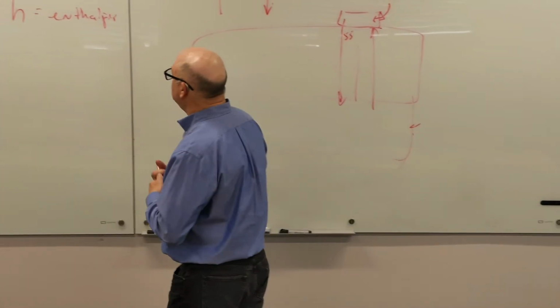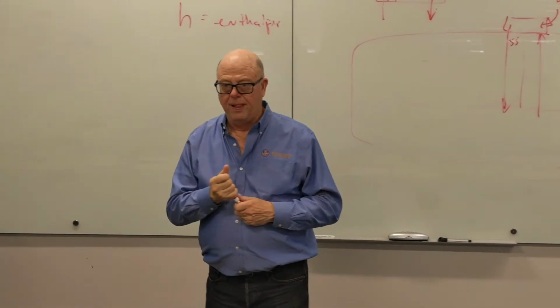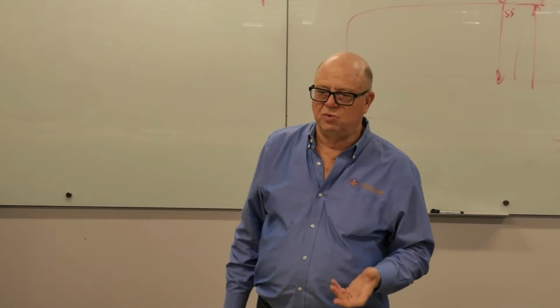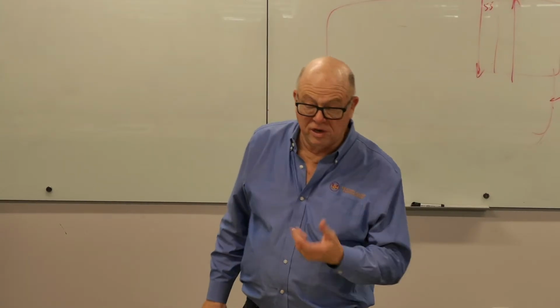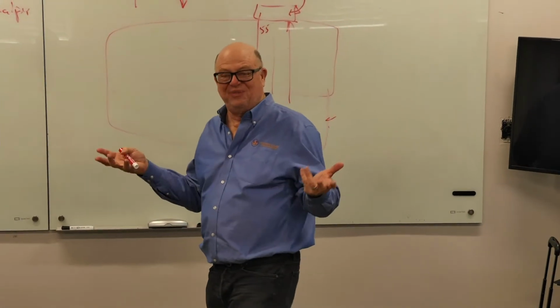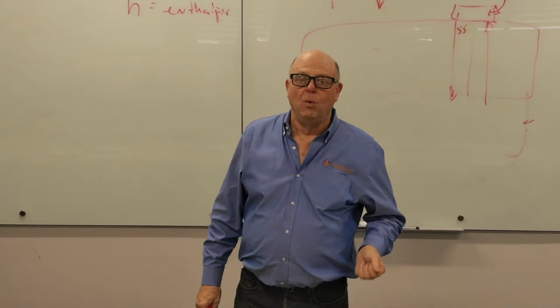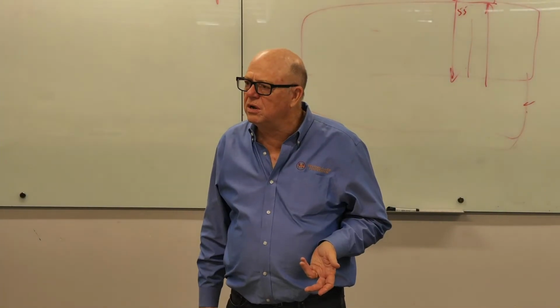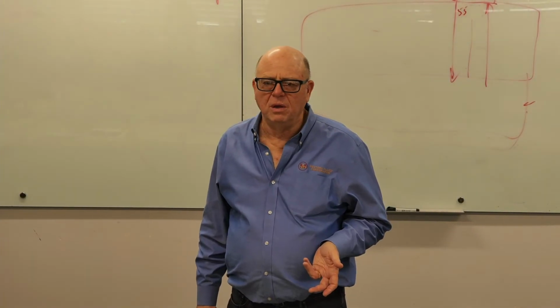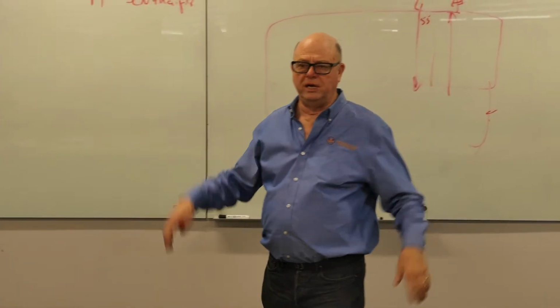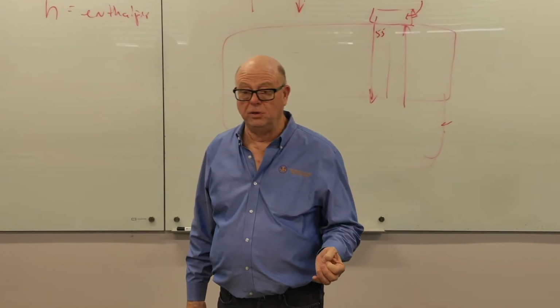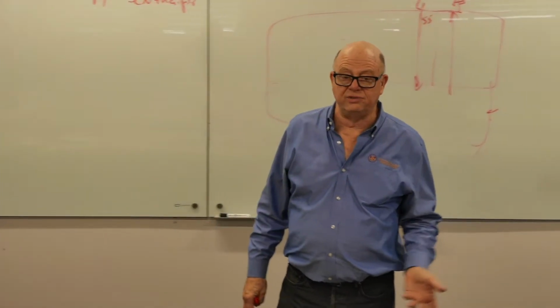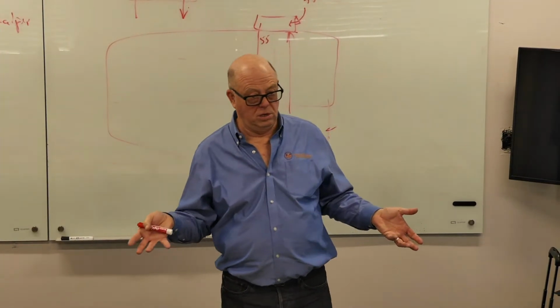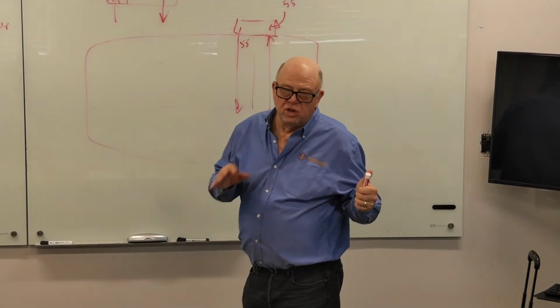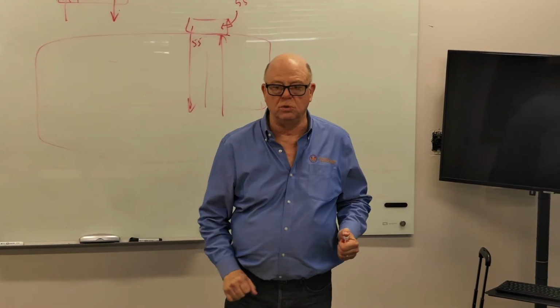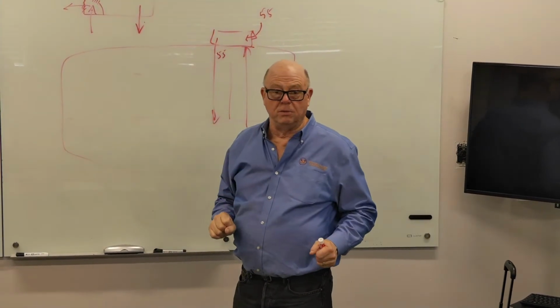So the thing in the 90s was switching over to enthalpy control instead of dry bulb. The problem there was that the sensors in the 90s were crap. The initial ones used animal hair. I mean, that was the very first ones. They just were junk, okay? When did we get a good enthalpy sensor? I'm not the person to ask that question. It was after Y2K. I'm going to say sometime in the aughts, probably. Today's enthalpy sensors are actually pretty good. They're reasonably accurate, and they don't just last 6 months. So there's nothing wrong, and the energy code wants you to use an enthalpy sensor rather than a dry bulb sensor.